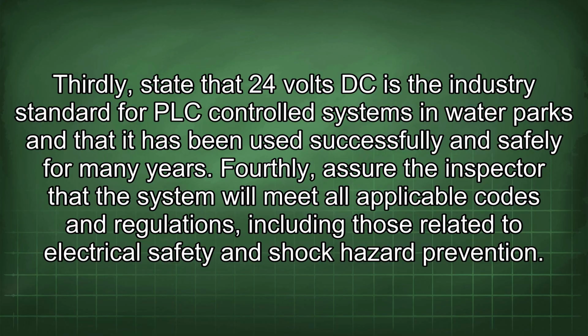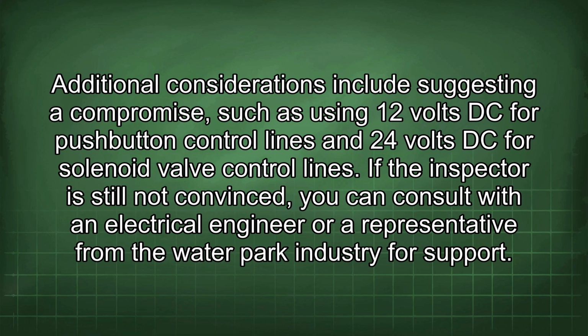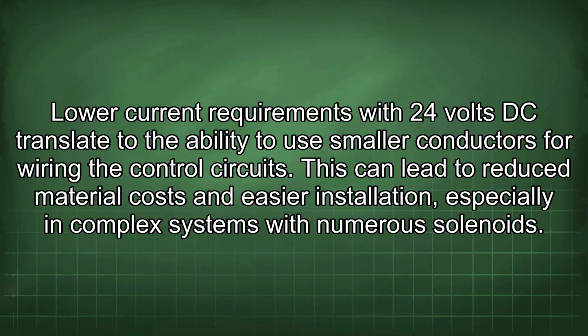and shock hazard prevention. Additional considerations include suggesting a compromise, such as using 12 volts DC for push-button control lines and 24 volts DC for solenoid valve control lines. If the inspector is still not convinced, you can consult with an electrical engineer or a representative from the water park industry for support.